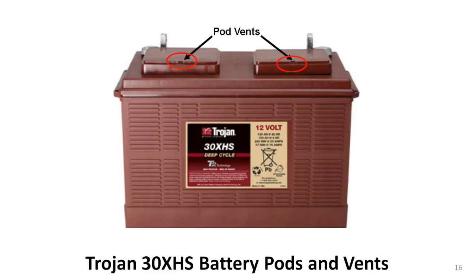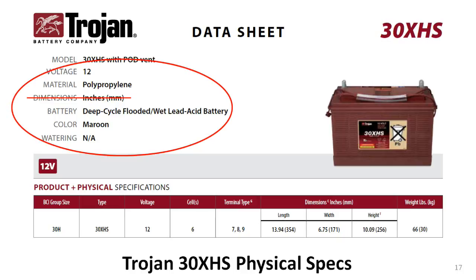The electrolyte is a sulfuric acid solution, so letting it get outside the battery is a very bad idea — it will burn your skin, your clothes, and most everything else it touches. Don't do it. The next few lines tell you that the battery is a 12-volt model, the case is made of polypropylene, it is a deep cycle flooded lead-acid battery, and it's maroon in color. The dimensions line tells you nothing useful. The watering line refers to a system of tubes for adding water to each cell; the 30XHS does not have this feature.